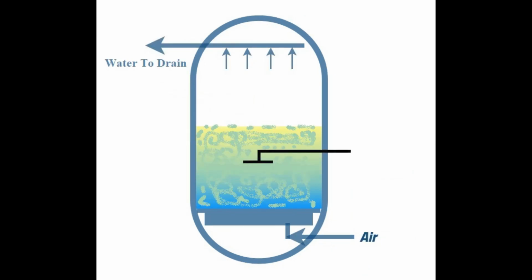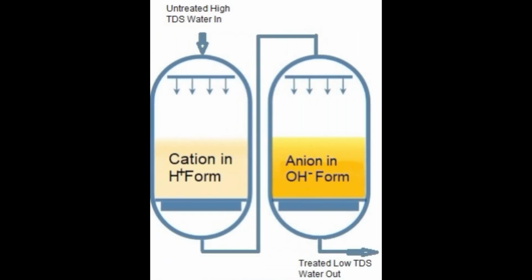There are two technologies available, two-bed ion exchange and mixed-bed ion exchange. The advantages lie in the capacities, ease of transport, and in some applications purification quality. This article focuses on mixed beds, or mixed resin deionization. The mixed bed is easier to manually transport and fill. The use of mixed resin treats the incoming water to a lower TDS than a two-bed spot-free DI. The two-bed DI will have a slightly better capacity before the resin needs to be changed out. Both will produce spotless rinses, but both are expensive to operate in comparison to a water softener.